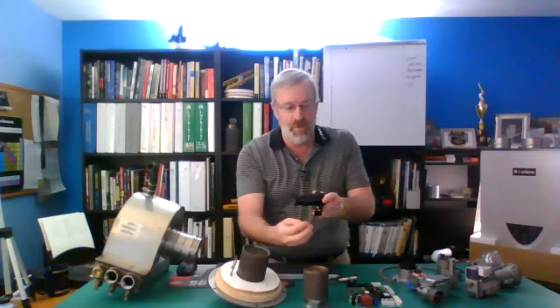So I just thought it was a nice way to take a look at it. And this right here is that adjustment. This is the main adjustment of that gas valve, if you will. We're adjusting the gas-air mixture. As we tighten this down along here, that changes how much gas we're pulling and mixing in there. And for those of you that are familiar with it, that brass screw that you see goes right here inside of this venturi.